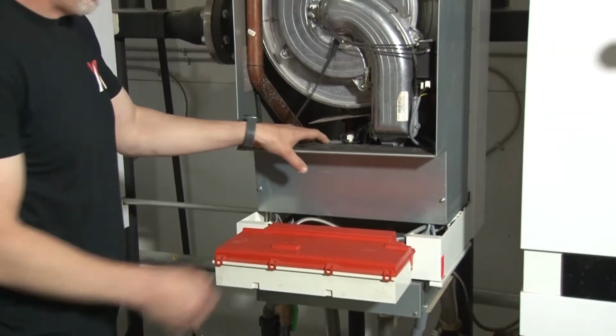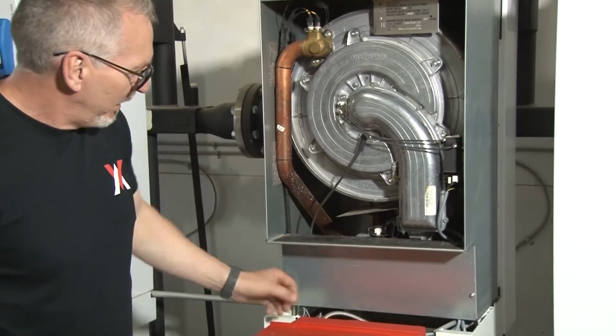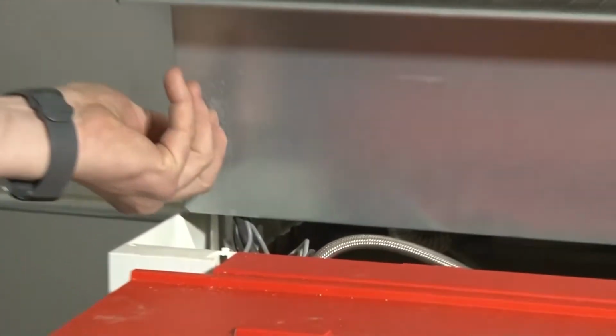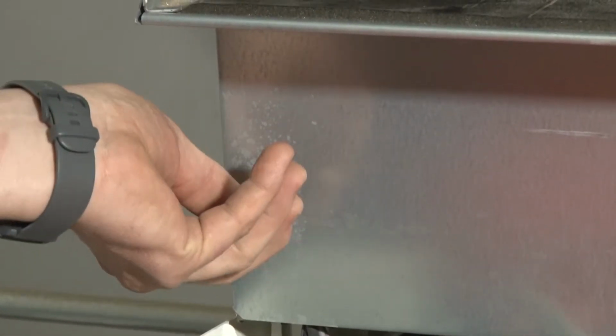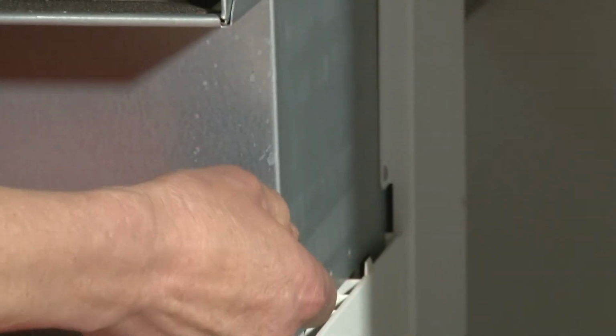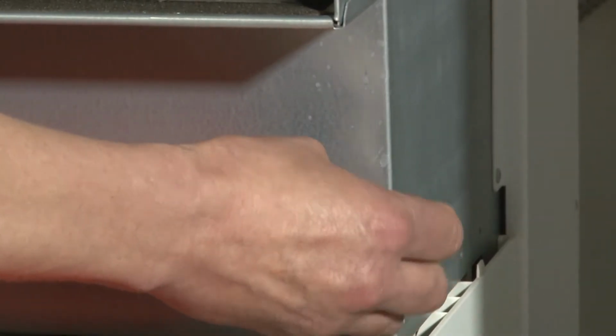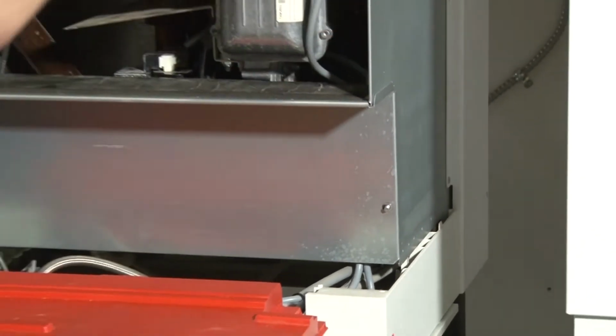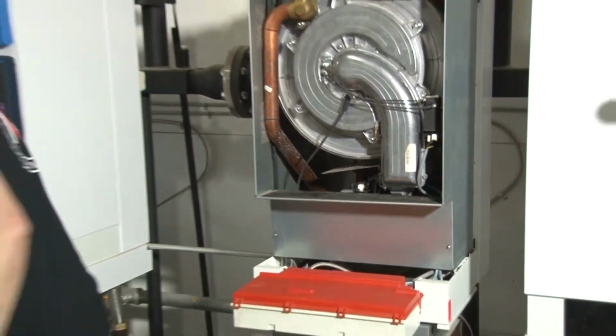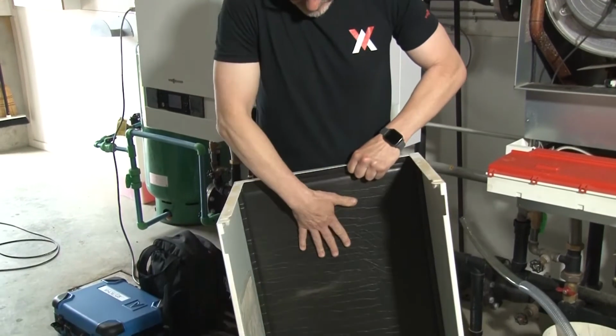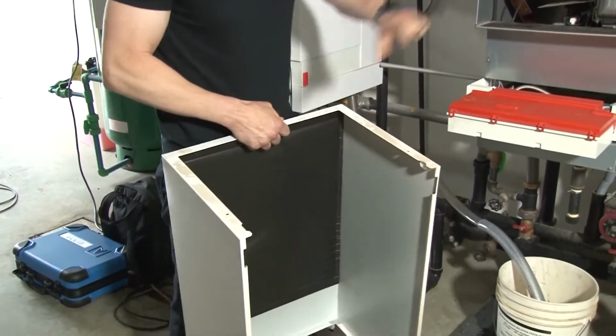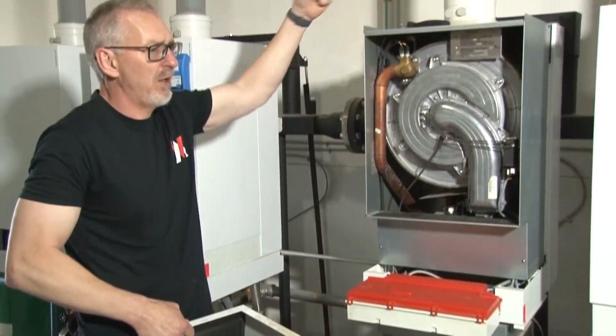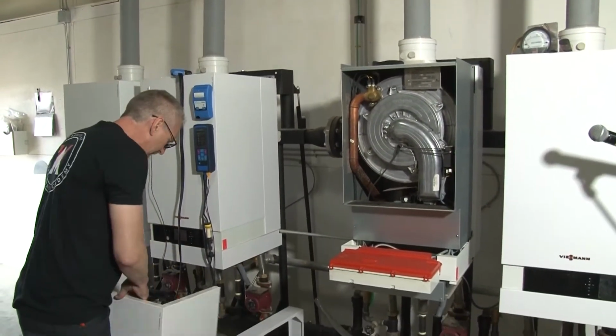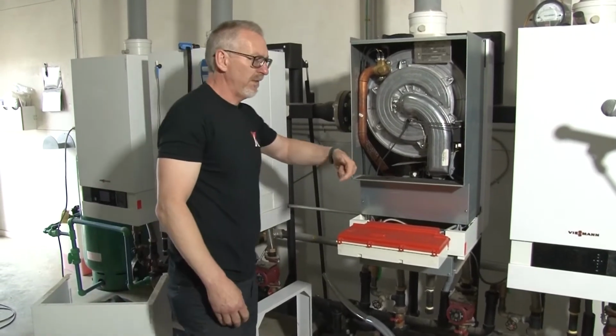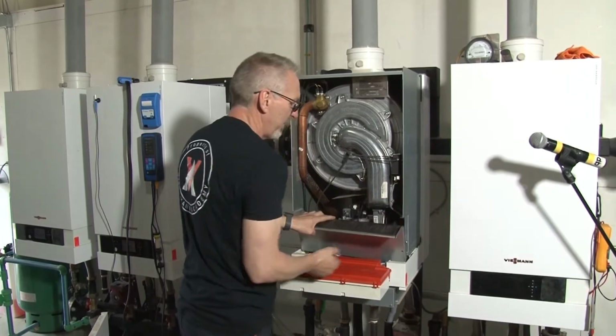Then we have this little combustion air angle plate here. And it's held on by two 8mm nuts. I've kind of loosened those up a little bit to make it easier for me to pull those out. So we take those little nuts out. The reason why this is here is when I put the enclosure back on and tighten it down with the Phillips head screws, this is a sealed area. On the back of your door here, you've got this little line of acoustic insulation. So when I put that in, that seals this combustion area. So if I'm pulling my air from outside, I've got a direct connection, a combustion air pipe, I'm not basically pulling air from the room. I just pop this little cover off the side.